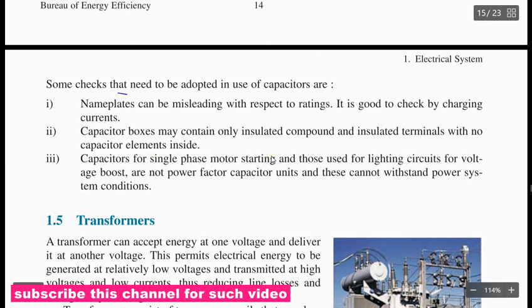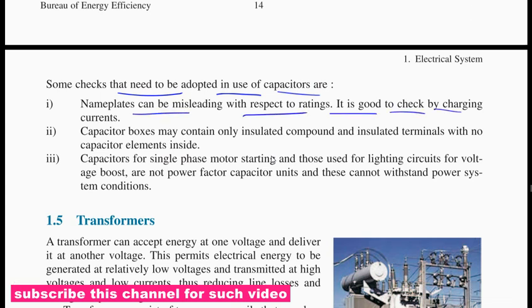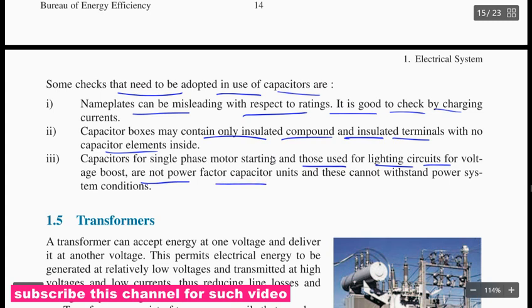Some checks that need to be adopted in the use of capacitors. Nameplate can be misleading with respect to rating. It is good to check by charging current. Capacitor boxes may contain only insulated components and insulating terminals with no capacitor element inside. Capacitors for single phase motor starting and those used in lighting circuits for voltage boost are not power factor capacitor units. These cannot withstand power system conditions.